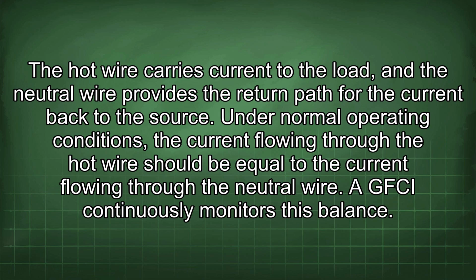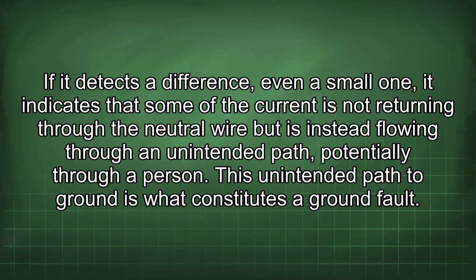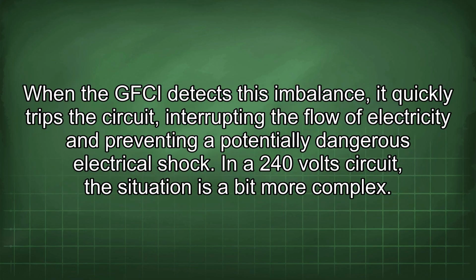A GFCI continuously monitors this balance. If it detects a difference, even a small one, it indicates that some of the current is not returning through the neutral wire but is instead flowing through an unintended path, potentially through a person. This unintended path to ground is what constitutes a ground fault. When the GFCI detects this imbalance, it quickly trips the circuit, interrupting the flow of electricity and preventing a potentially dangerous electrical shock. In a 240-volt circuit, the situation is a bit more complex.